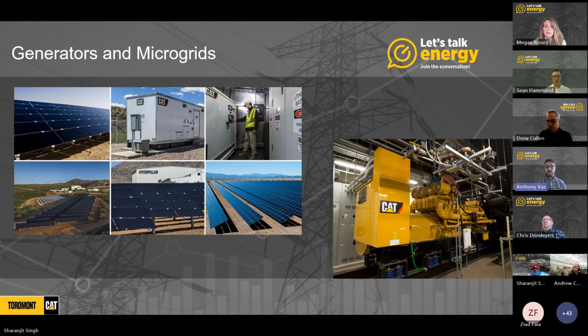So to get the most out of the generator, as Chris mentioned, to avoid wet stacking, generators should run at around 70% load or higher—that's where they're most efficient. Whether it's natural gas in the city or diesel in remote areas, it's all about finding the right balance between reliability, efficiency, and sustainability.